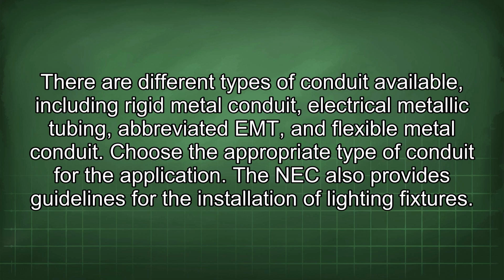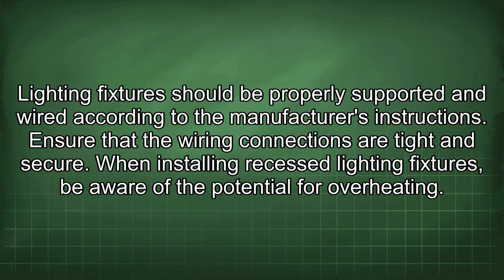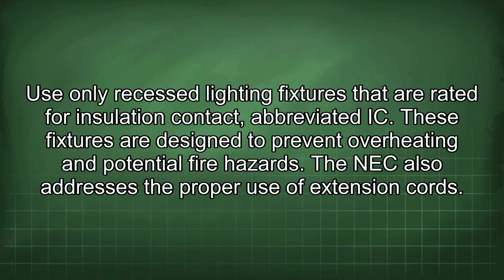The NEC also provides guidelines for the installation of lighting fixtures. Lighting fixtures should be properly supported and wired according to the manufacturer's instructions. Ensure that the wiring connections are tight and secure. When installing recessed lighting fixtures, be aware of the potential for overheating. Use only recessed lighting fixtures that are rated for insulation contact, abbreviated IC. These fixtures are designed to prevent overheating and potential fire hazards.